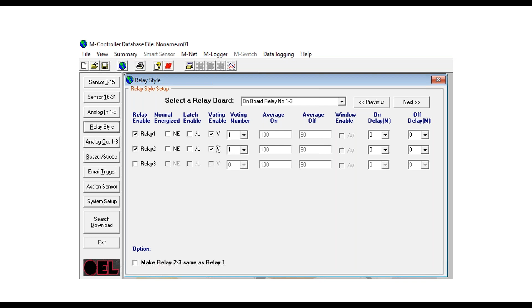So right here, this is where we're assigning the sensors to relay 1. And as we can see here, this is alarm level 1. We have 35 parts per million for CO to turn on, 25 to turn off. For NO2, we have 1 part per million to turn on, and it'll turn off at 0.8. So again, this is relay 1, and we'll do the same thing for relay 2.